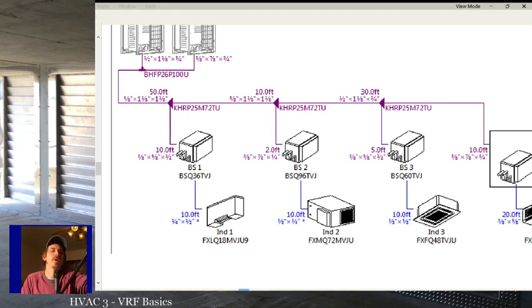If you ever take a VRF class or talk to a VRF tech, somebody who works for a manufacturer or something, they love talking about when they have the plumbers do the line set. The line sets look real pretty, but the plumbers put in 40 90s and nothing works right. It happens. When it comes to VRF and mini splits, but especially VRF, my rule is I don't want it to be pretty, I want it to be practical. It should be good workmanship, you should do a good job, you should make it look as good as you can, yes. But if it's going to be a little bit uglier, if I can just beeline it from the Y kit to the indoor unit, or I can make it look real pretty by adding 3 90s, I'm just going to beeline it.